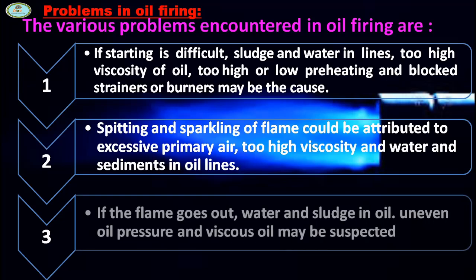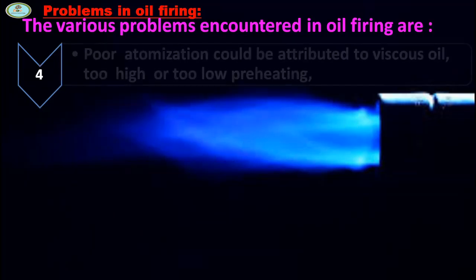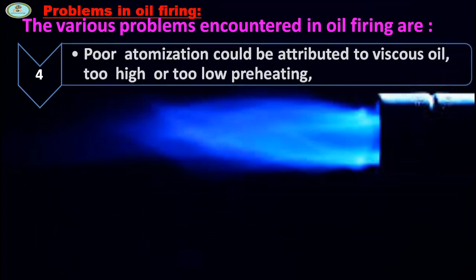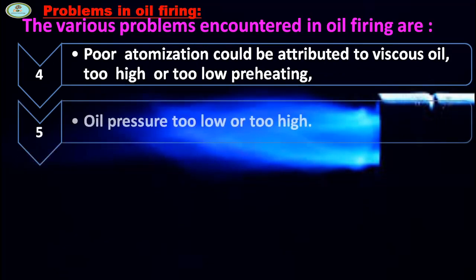If the flame goes out, water and sludge in oil, uneven oil pressure, and viscous oil may be suspected. Poor atomization could be attributed to viscous oil, too high or too low pre-heating, and oil pressure too low or too high.